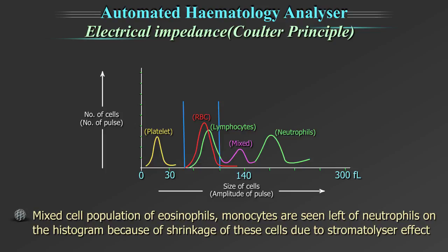However, the mixed cell population of eosinophils and monocytes are seen to the left of the neutrophils on the histogram, because of the shrinkage of these cells due to the stromatolyser effect.